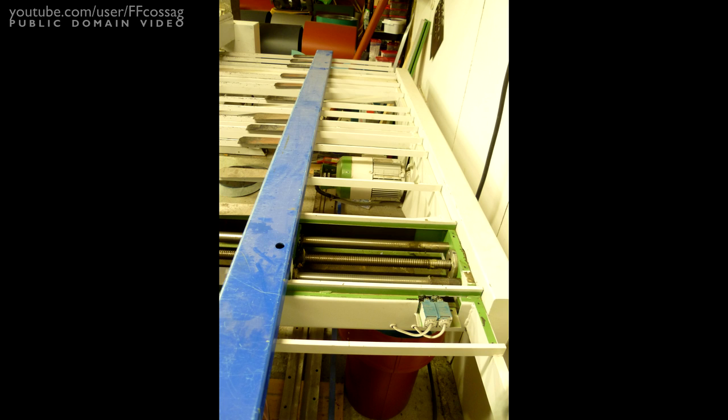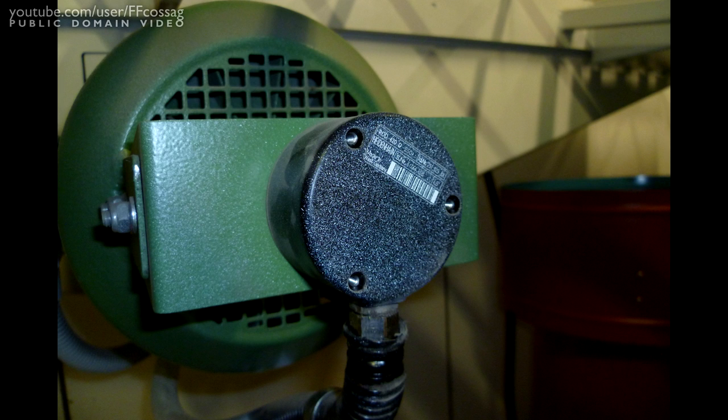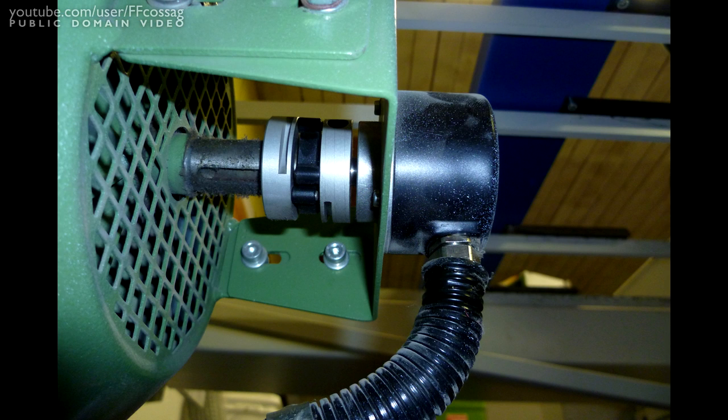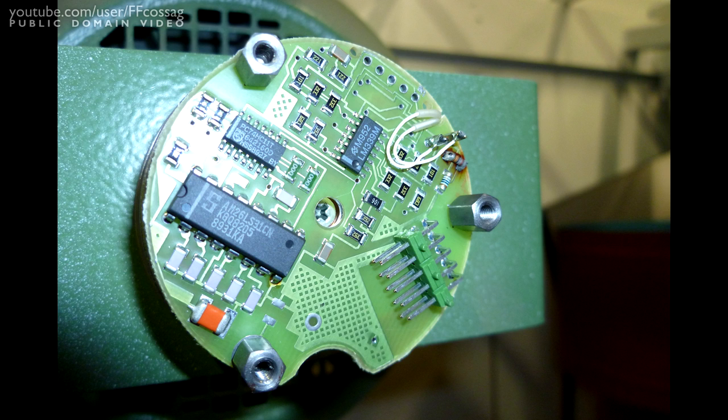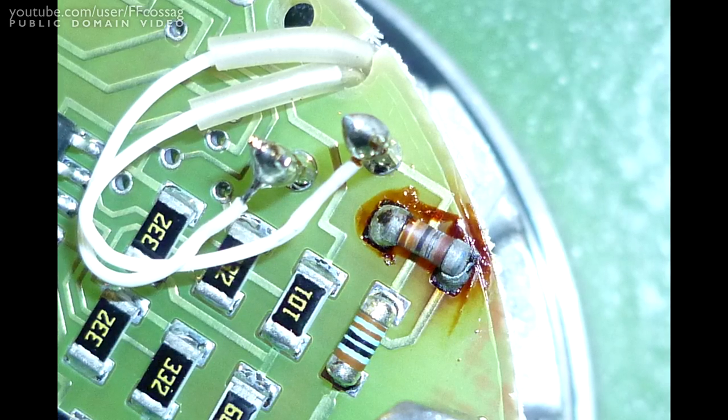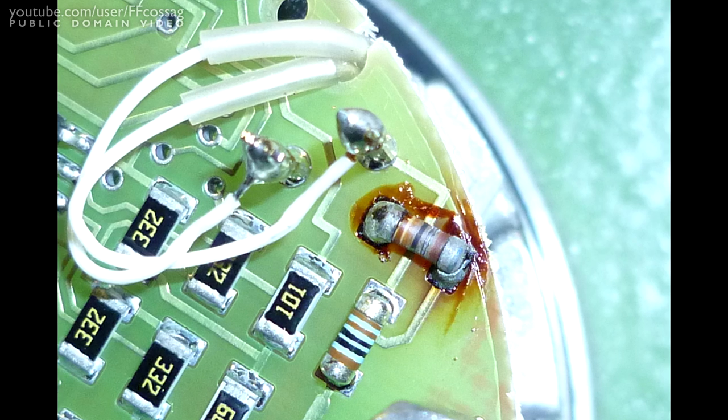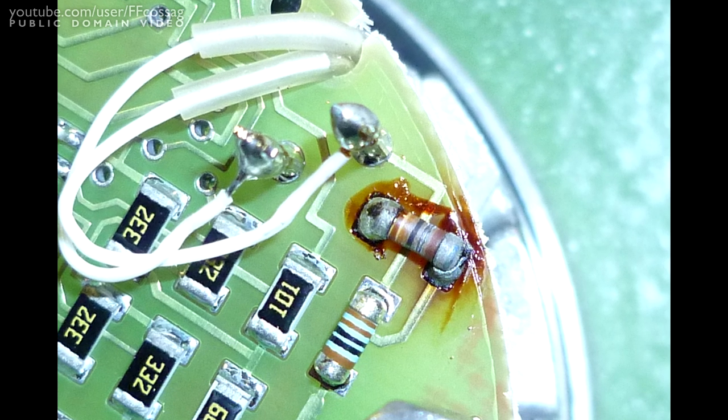So I sat down to chasing and looking around the machine for any rotation sensors, any pulse sensors, stuff like that, attached to any shafts. And sure enough, hidden under a cover on the main big AC three-phase motor, there was a pulse thing-amajig, pulse sensor. And once I took that apart, sure enough, there was a broken solder joint, the thing wasn't getting any power. So I just prodded it with a soldering iron, and bloody hell, the machine started working just fine, and that's been the issue all along - a bad solder joint on the pulse sensor.